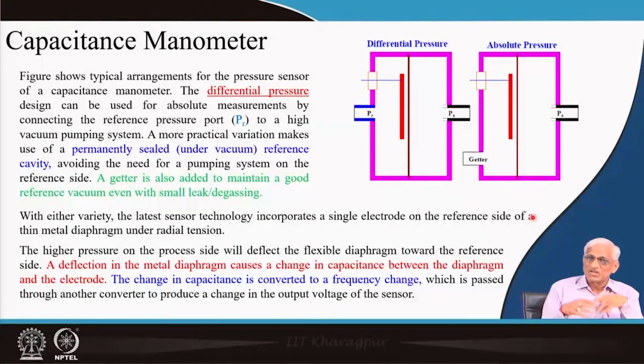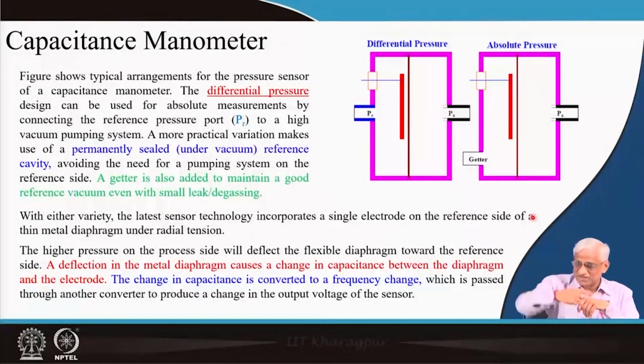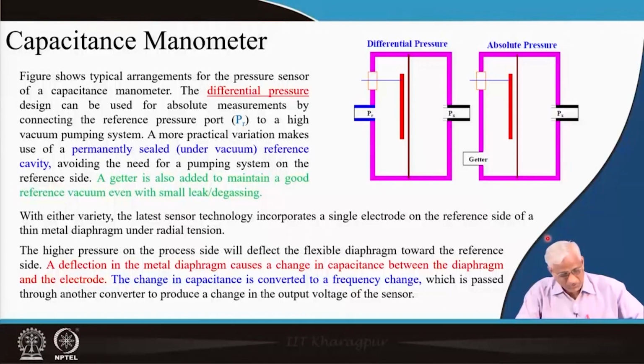So, deflections, how to convert them electronically? One way is through the capacitance manometer. This is also basically a deflection manometer like the C tube type Bourdon gauge, but it gives a signal instead of a mechanical indicator with a coupling as in the Bourdon gauge. Here it gives a signal. How? You can read, I am not going to read this. This is a small pillbox type thing, a small circular box having two chambers separated by a thin diaphragm.